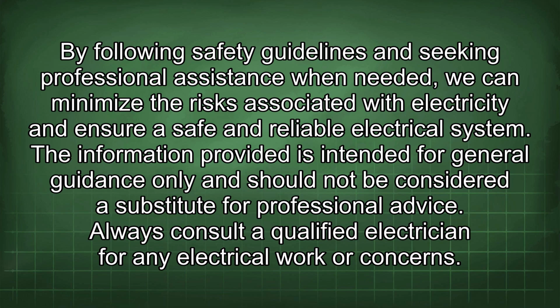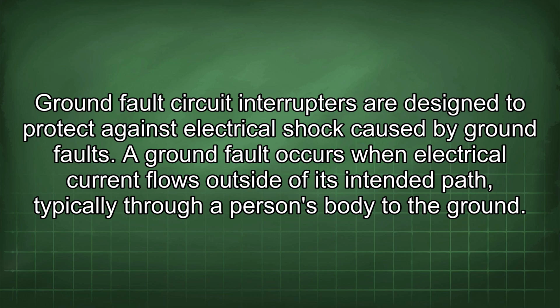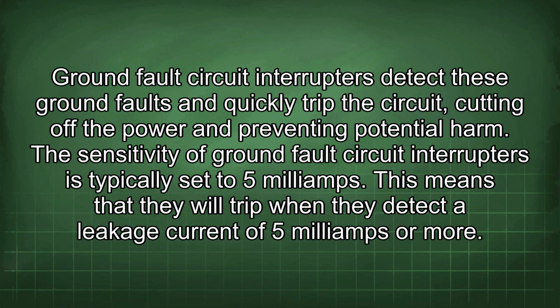The information provided is intended for general guidance only and should not be considered a substitute for professional advice. Always consult a qualified electrician for any electrical work or concerns. Ground fault circuit interrupters are designed to protect against electrical shock caused by ground faults. A ground fault occurs when electrical current flows outside of its intended path, typically through a person's body to the ground. Ground fault circuit interrupters detect these ground faults and quickly trip the circuit, cutting off the power and preventing potential harm. The sensitivity of ground fault circuit interrupters is typically set to 5 mA.